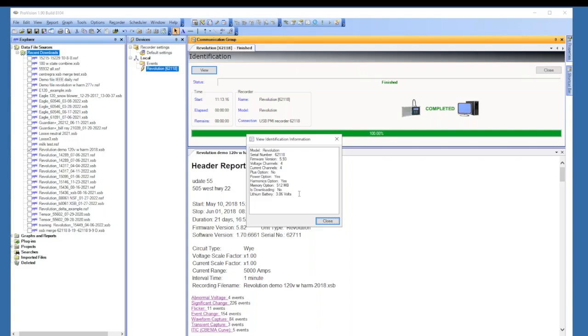So this is real important that you do this before you send the recorder out. If the battery is getting down around 2.6 volts, ProVision will start to complain. You'll see a little pop-up there that says critical battery voltage, but to check, just go ahead and look there. If it is around 2.6 volts, you probably have a few months, so if you really need it, you can still get a recording out of it, but it would be best to send it in and get the battery replaced at that time. It's critical that you do that so that you don't lose any data.